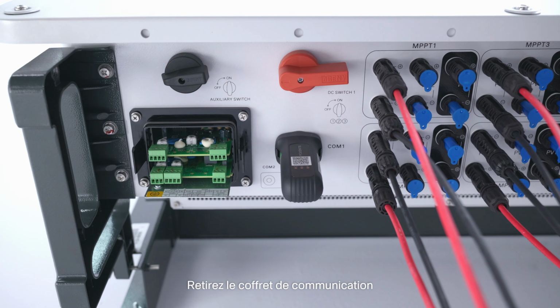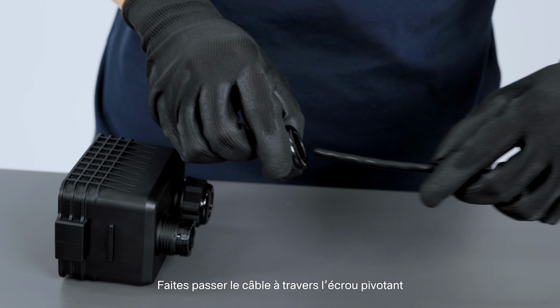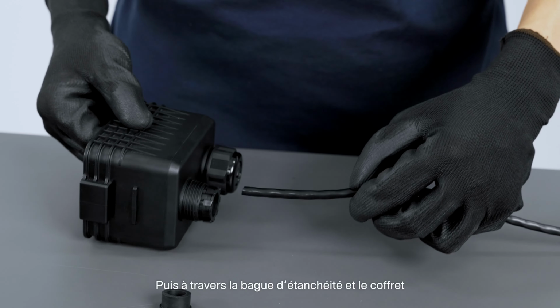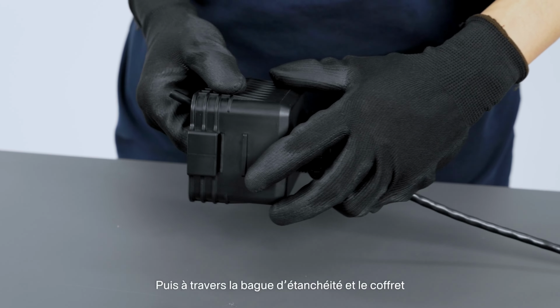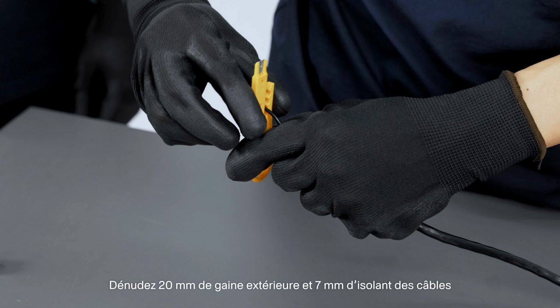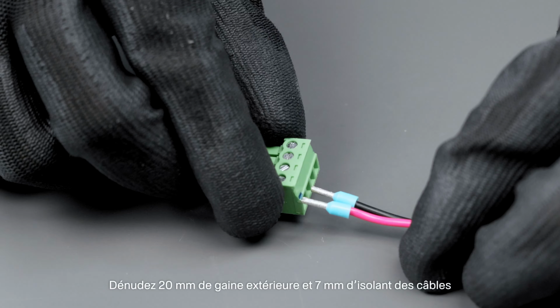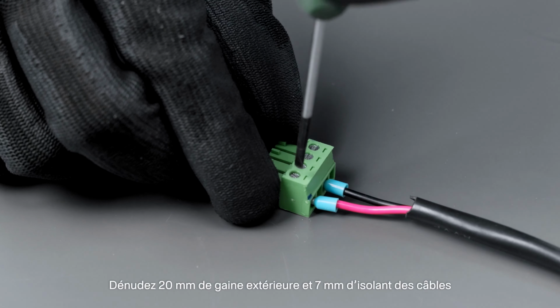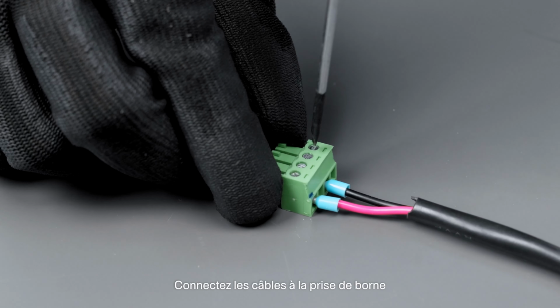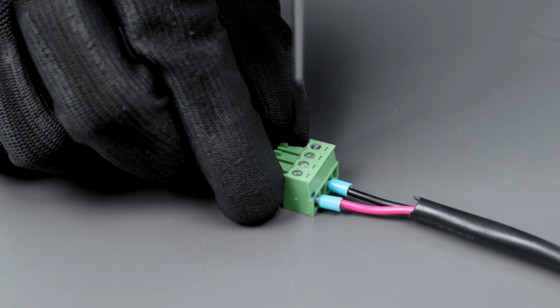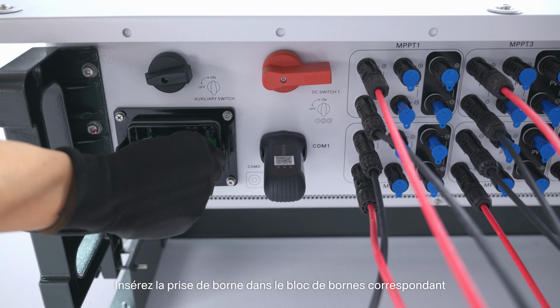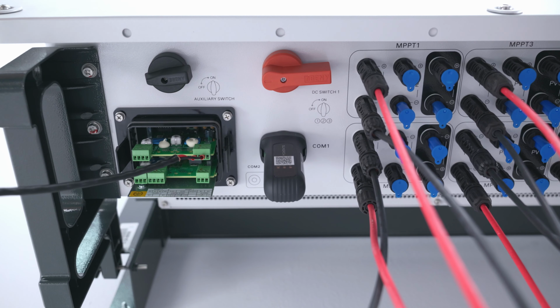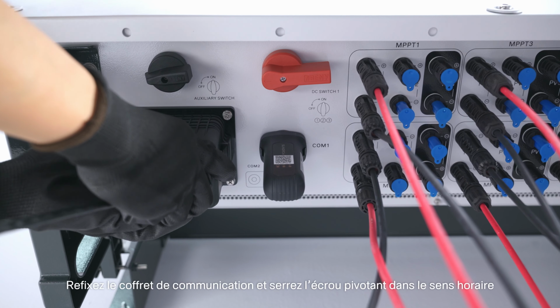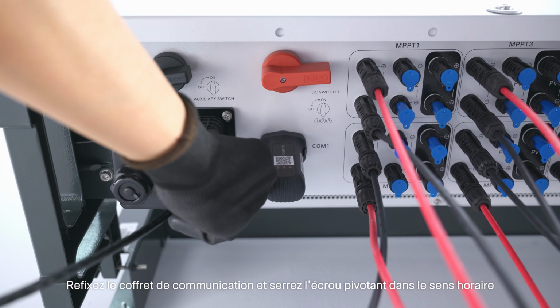Remove the communication junction box. Lead the cable through the swivel nut, the sealing ring, and the junction box in sequence. Strip the 20 mm protective layer and the 7 mm insulation layer off the cables. Connect cables to the terminal socket. Insert the terminal socket into the corresponding terminal block. Install the communication junction box and screw the swivel nut clockwise.